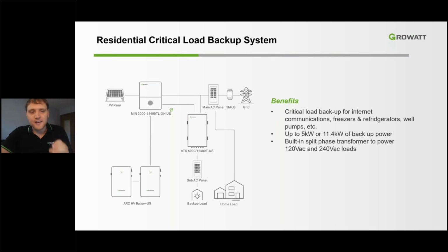The batteries are not entirely necessary for this system. Again, this is a battery-ready inverter, so they can be installed PV only first, upgraded to the battery system later, and it's not totally needed for the ATS system. The PV production can power the ATS.